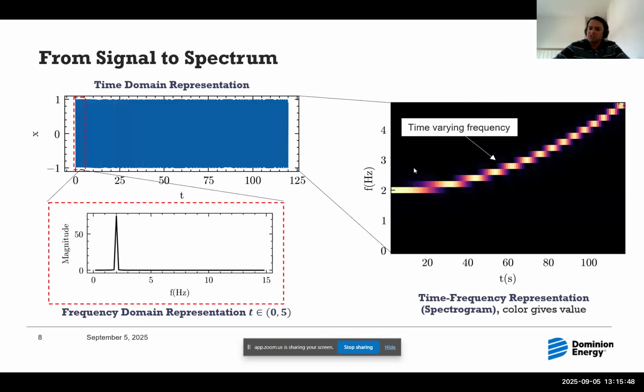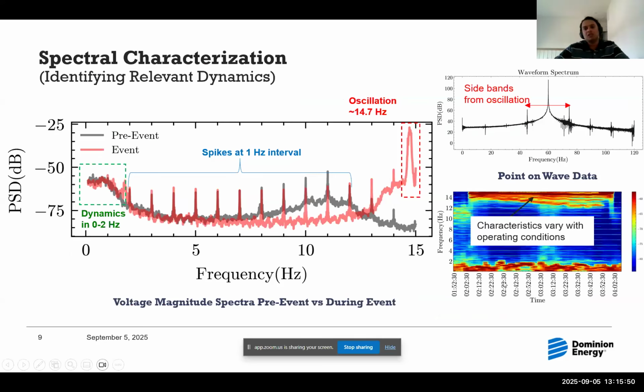And this particular oscillation is essentially responding to that operating condition, meaning this oscillation's characteristic is a function of where we are operating, which is very commonly seen in control-created oscillations, the oscillations that are not feed forward but have a feedback component to them, so that they respond to the grid conditions. So a small clue, but something to not ignore. When we're investigating, we have to gather all clues around the oscillation to figure out what's going on.